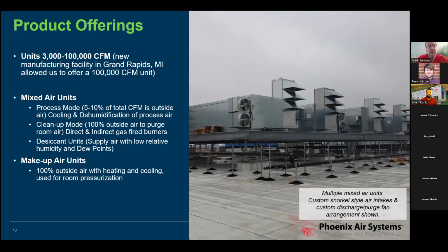They're sanitizing everything, and then they're going to start back up in 4 hours from the time they start to get the room down to temperature, and certainly all the condensation off the ceiling. That's where that mixed air unit with the flip of a switch goes from a little bit of outside air to all outside air. We want to basically flush the room out. When we talk about the 3-minute air change, the simple math is this. Take your square footage of the room, multiply it by the ceiling height.